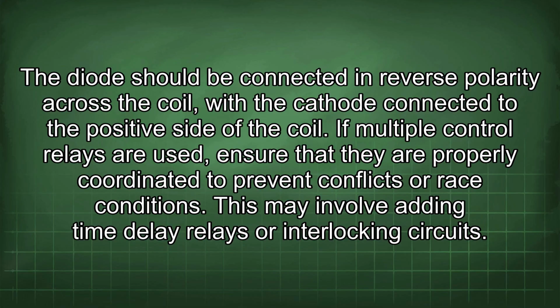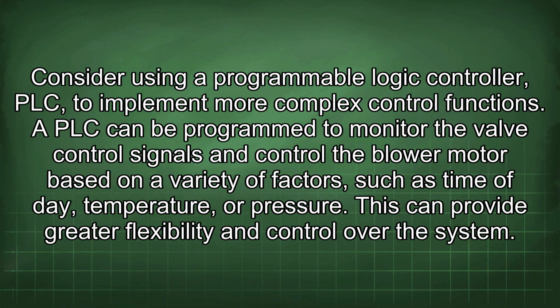If multiple control relays are used, ensure that they are properly coordinated to prevent conflicts or race conditions. This may involve adding time delay relays or interlocking circuits. Consider using a programmable logic controller (PLC) to implement more complex control functions. A PLC can be programmed to monitor the valve control signals and control the blower motor based on a variety of factors, such as time of day, temperature, or pressure. This can provide greater flexibility and control over the system.